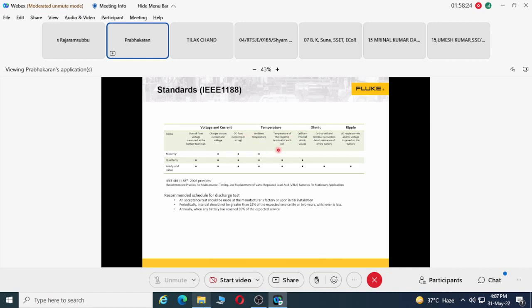Temperature is important because the ambient temperature, and when the electrolysis process happens, there's an increase in temperature. These two temperatures can deteriorate the electrolysis process as well as the electrolyte inside a battery. That's why temperature monitoring matters. Especially in our system, the negative probe is also equipped with a temperature sensor, so you can get the temperature present at the negative pole.